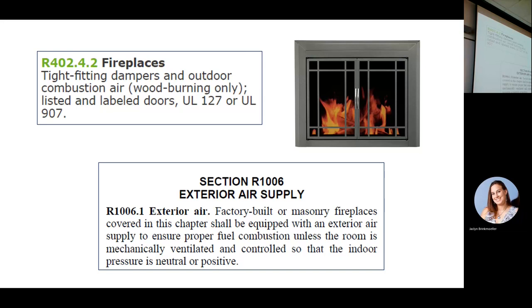And it says that a factory built or masonry fireplace shall be equipped with all these things to ensure proper combustion unless the room is mechanically ventilated and controlled so that the indoor pressure is neutral or positive. How do you have a fireplace burning that doesn't take the building or the room negative pressure? It's almost impossible unless you have a makeup air system.